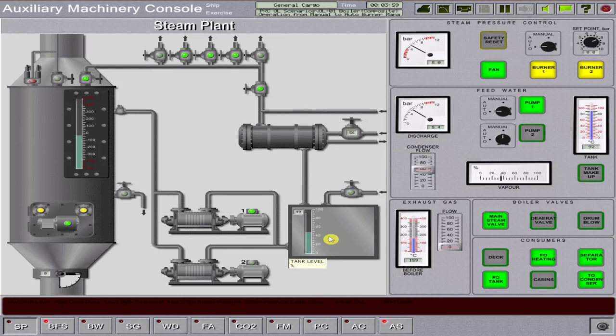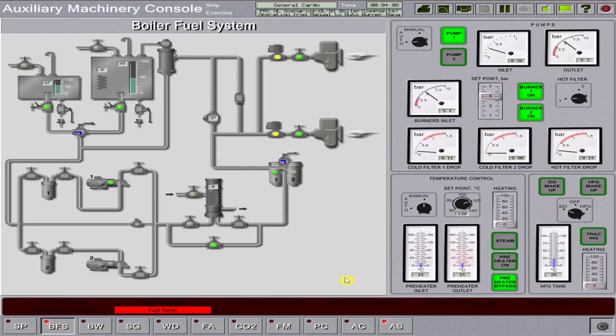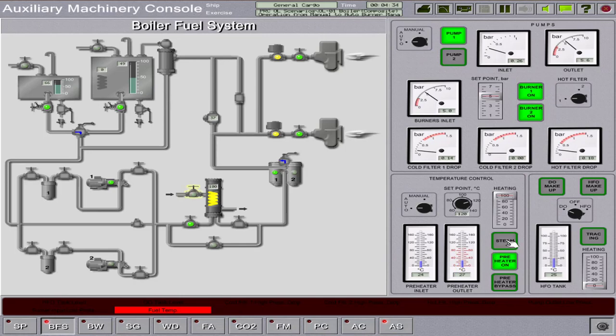Now we change over the fuel from diesel oil to heavy oil. Proceed back to your boiler fuel system. Set the temperature controller first to automatic running, then open your preheater inlet valve. Close your steam bypass valve. To rectify the alarm, open the steam inlet valve going to the preheater, then watch the preheater outlet temperature rise. Once it reaches around 120 degrees centigrade, the alarm will be cancelled. Once the alarm has been cancelled, you can now change over from diesel oil consumption to heavy fuel oil.